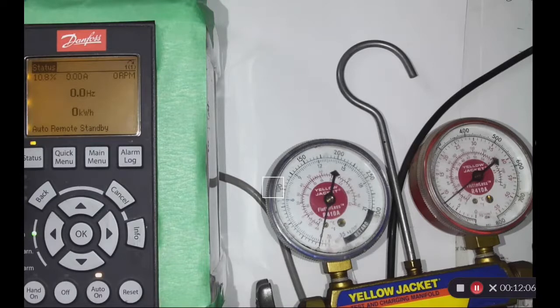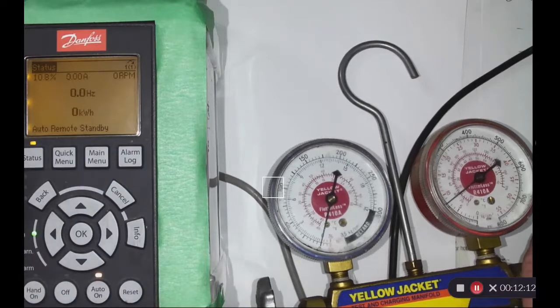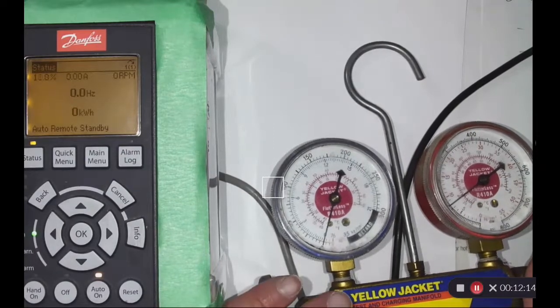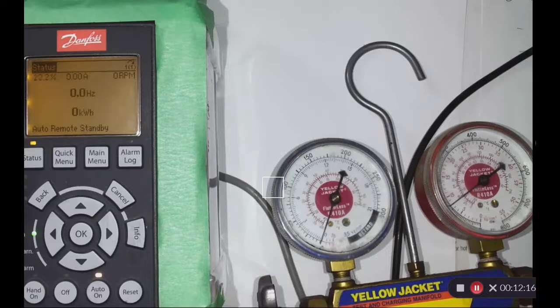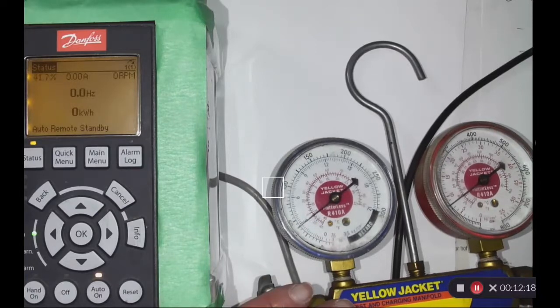Kind of cool. I'll just show you one other thing here before I go. I can open up the pressure on the gauges to put pressure to the transducer, and without anything running, you can see that the percentage of it is seeing a command. That's why I knew I had it wired in right. When I finally put pressure to this low gauge, or the transducer, in other words, you could see that it did go to 100%, even though it's not asking to do anything.